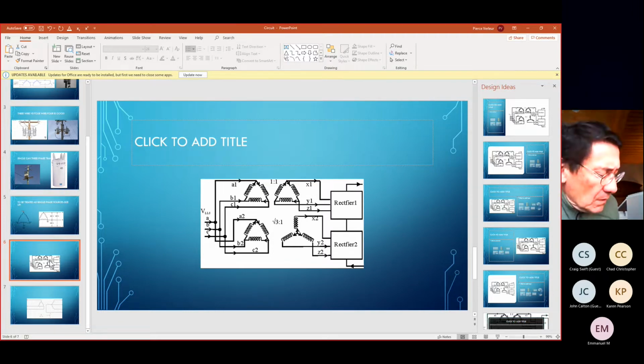And as such, a passive filter is going to work best in some circumstances and not best in others, as the line dynamics move away from the tuned point of the passive filter. If you're a catcher and you can't move your mitt, you're only going to catch a certain number of baseballs coming at you from the pitcher. This is the case here.